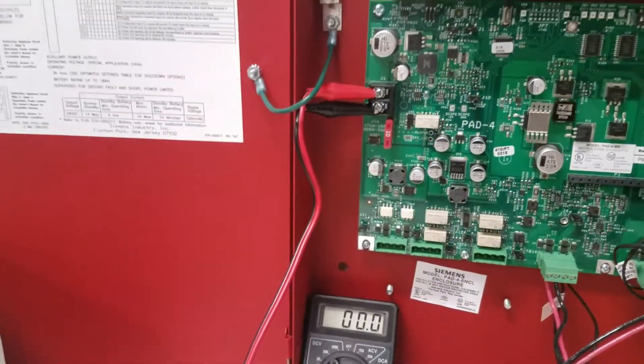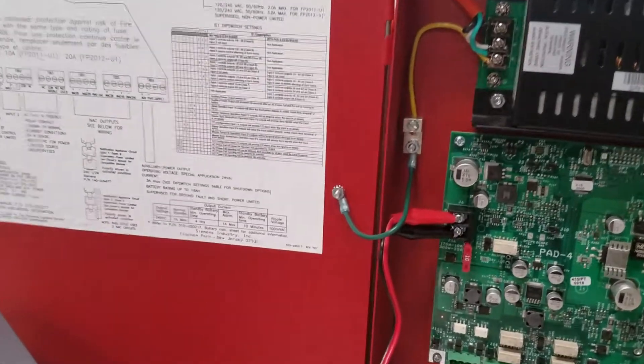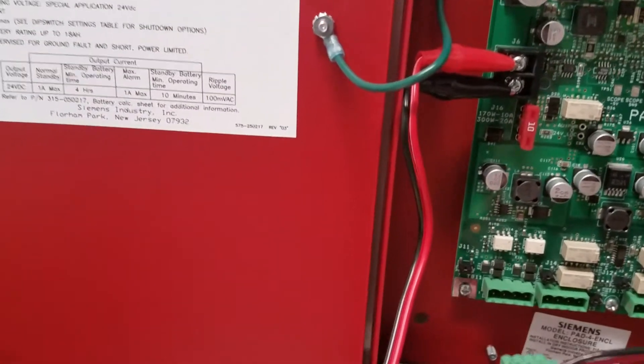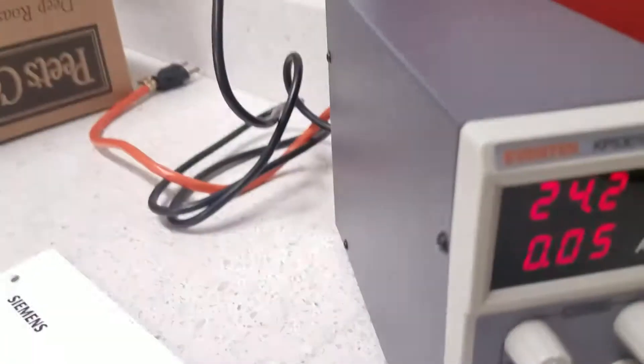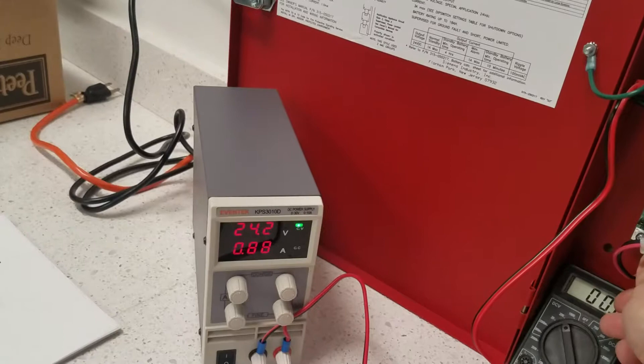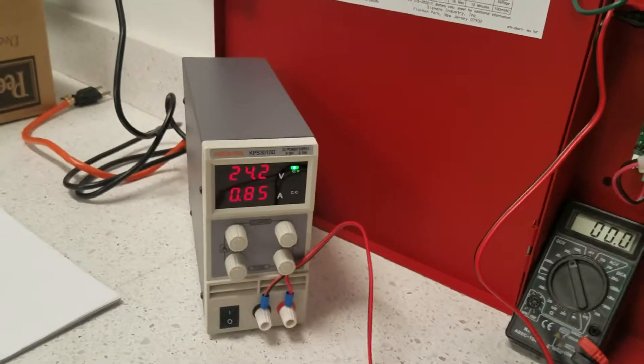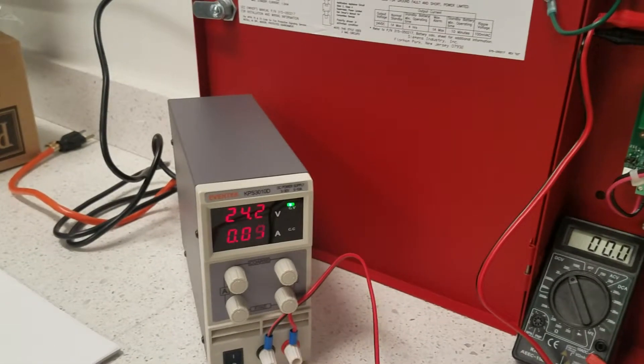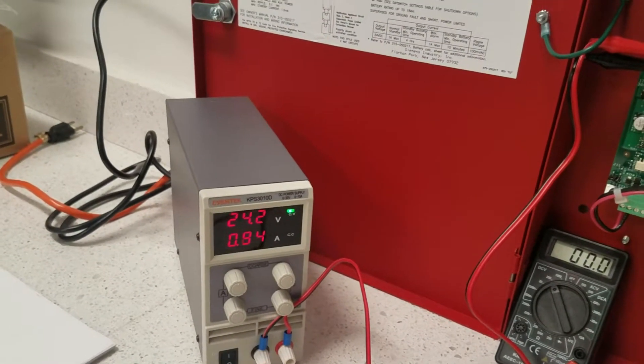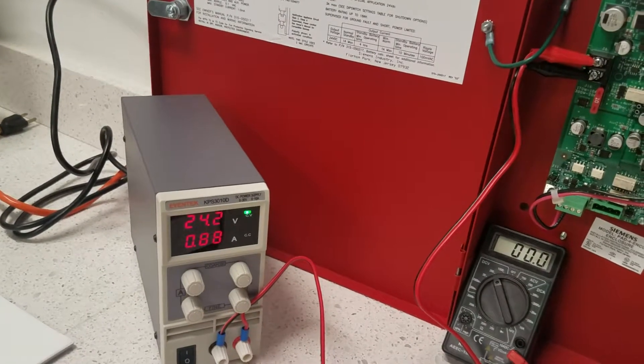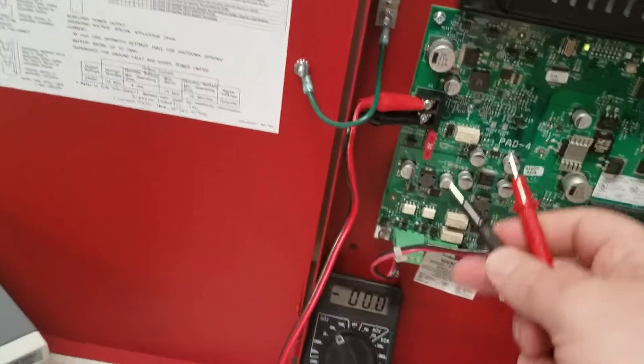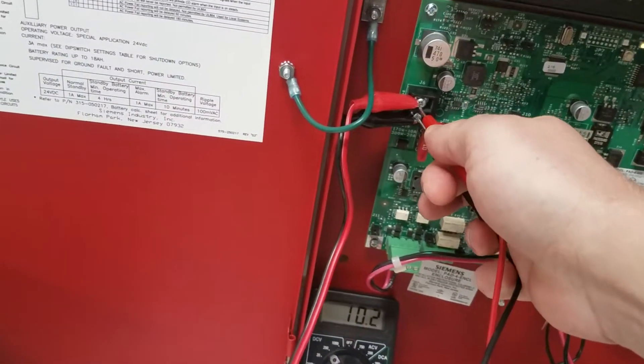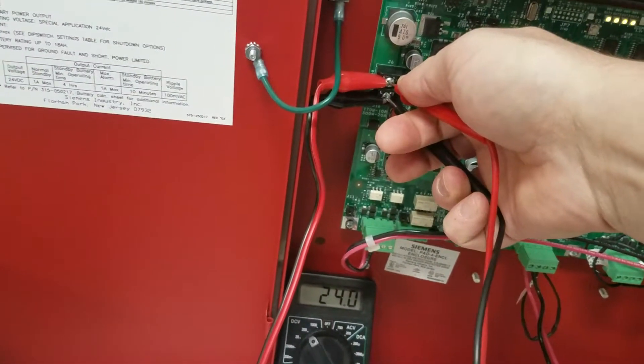So now what I want to do is I want to simulate the activation of the strobes. So we're going to activate the strobes and watch the power current as I plug this in. It steps up to 0.88, 0.94, just over one amp. So it is obviously pulling more current from the power supply now that the strobes have activated. And just to confirm again, the voltage on this, 24 volts, 24 volts even.